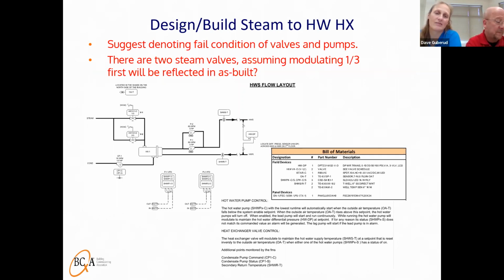So obviously this can vary depending on where you're from, but denoting the fail condition of your valves and pumps, in Wisconsin here, we might fail the 1/3 steam valve open. And so, just making sure that it's clear on how it should fail and that the right parts and pieces are in place. And what we're indicating there, even though it's pretty much, we'll say, virtually a given, but again, I think it's important to verbalize, with the 1/3, 2/3 valve arrangement, is it going to be the 1/3 valve that's going to be opening first? Because we believe it should be indicated. And again, for us to do it day in and day out, it's second nature. But what you have to potentially think about, right? If it's in a hospital, you have to think of that third shift guy that they just hired 3 weeks ago, that there's a problem with it. He can read the sequence of operation likely and get a better understanding of how it works.